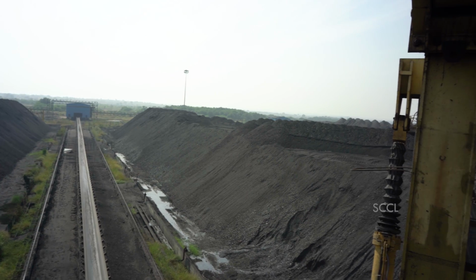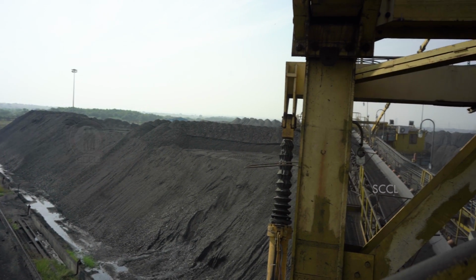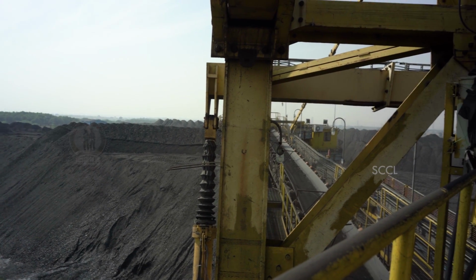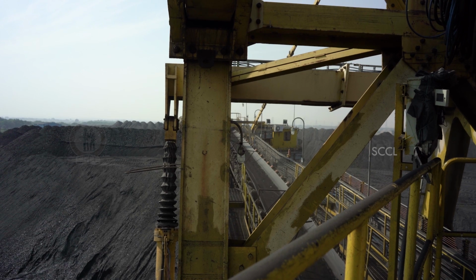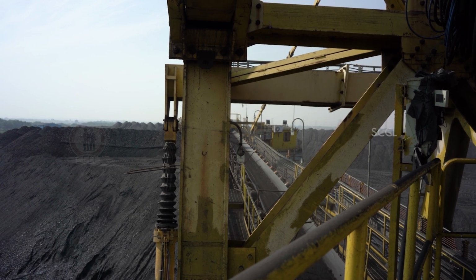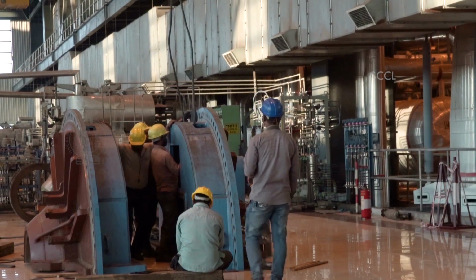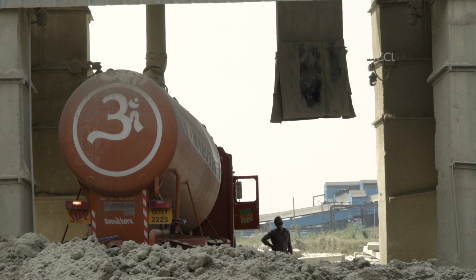STPP needs coal of G11 grade with 4,200 GCV with ash content of about 30%. If the coal is of lesser quality, more coal needs to be burned to produce the rated power, which increases the cost of production as well as ash percentage, which further creates problems in ash evacuation.